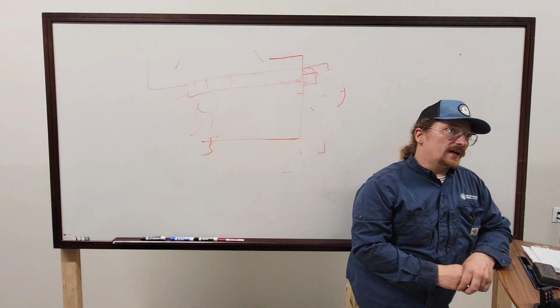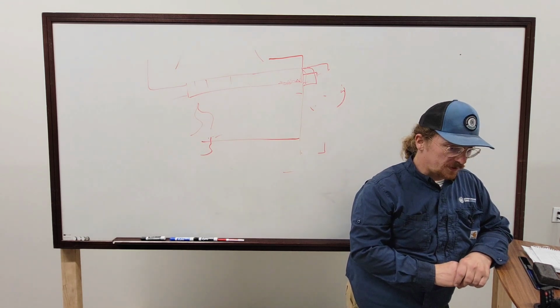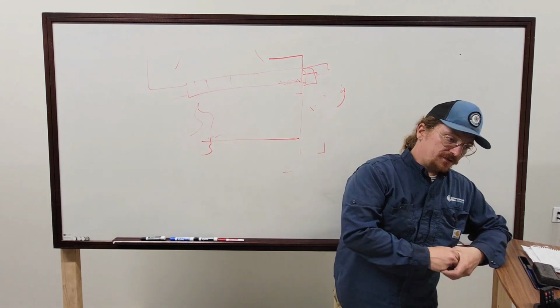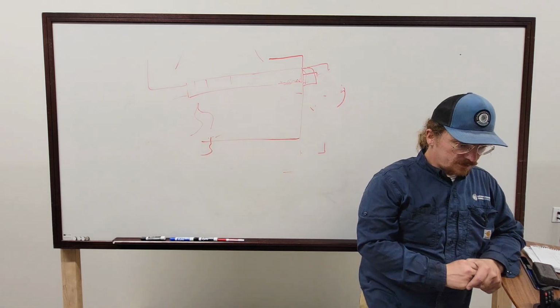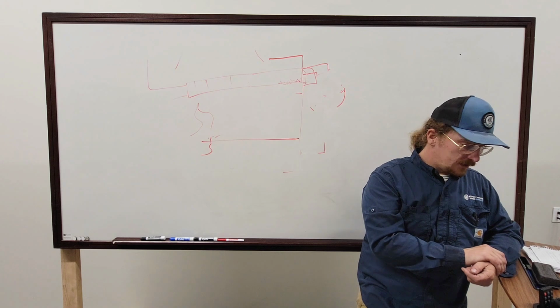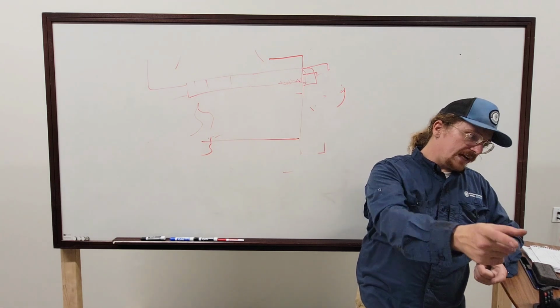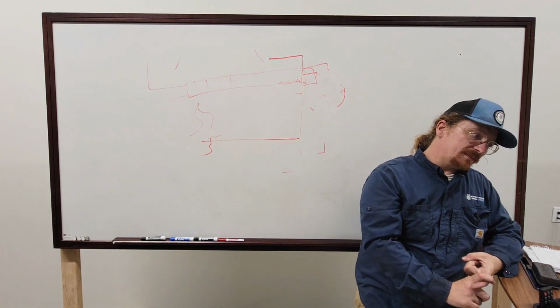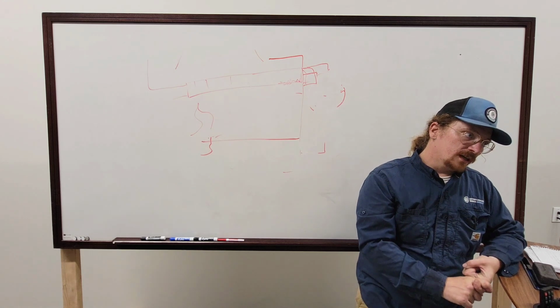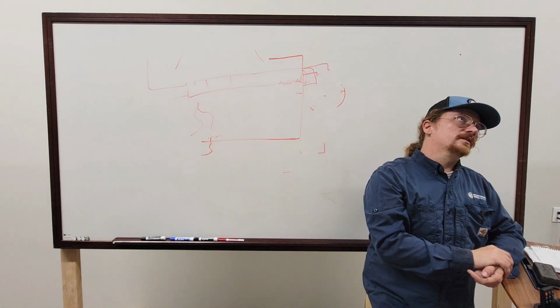But go clean the burner rack. Pull the burner rack, clean it, which may involve vacuuming it, may involve scrubbing it with soapy water. It depends on the material. Stainless steel, you can usually scrub with soapy water. Cast iron, you just want to vacuum. Flue gas analysis, measuring gas pressures, verifying we have proper gas pressures during high and low fire. And that's being compared to what the manufacturer wants.